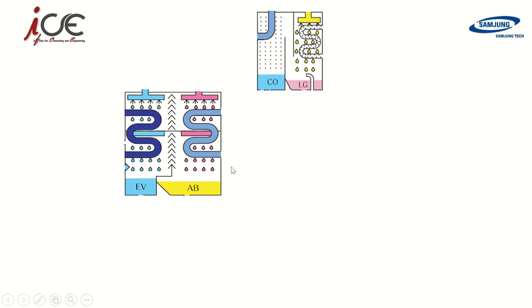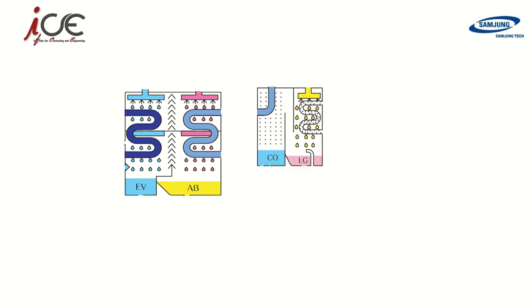The second shell contains the condenser and the low temperature generator. The condenser consists of a bundle of copper tubes where the water vapor is condensed. The low temperature generator also consists of a bundle of copper tubes. Inside it, steam is generated from a diluted solution which is heated by steam generated in the high temperature generator.